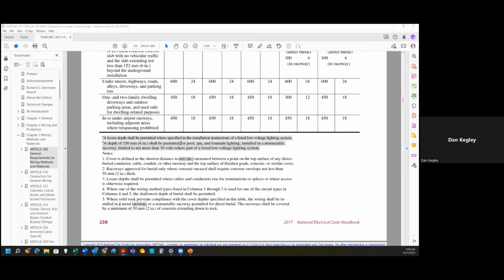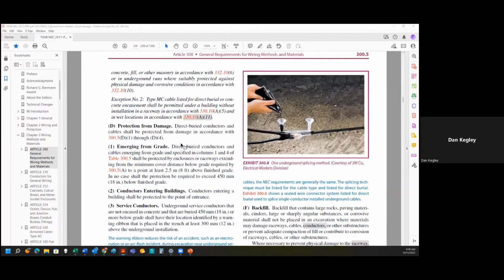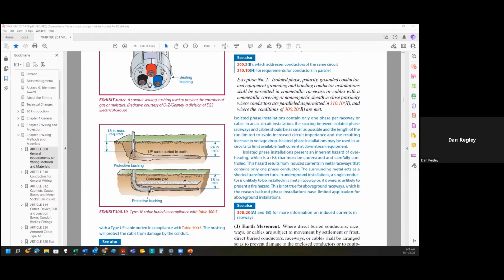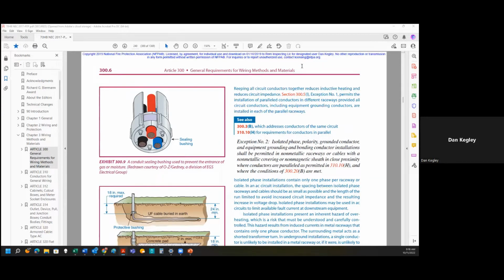Okay. So that kind of covers a little bit about that. And maybe that frost sleeve and that bushing on the end of the conduit. Another note is that this is a PVC conduit, not a PVC plumbing pipe. So you got to make sure you're installing wires inside the gray conduit and not inside the white PVC pipe. The code does require those conduits or raceways to be electrical PVC conduit. That's good to know. We see that happen quite a bit.